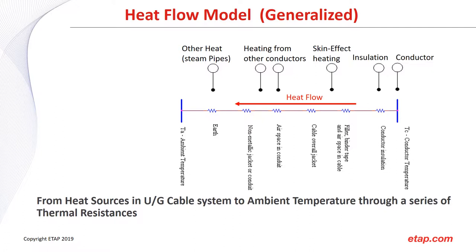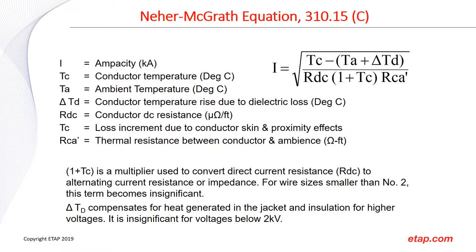The heat flow arrow goes from the conductor temperature, through conductor insulation, through filler, tape, air space in the cable, the cable overall jacket, air space in the conduit, the non-metallic conduit such as PVC, into the earth, and finally into the ambient temperature. All of these barriers need to be taken into account when doing thermal analysis. Both the NEC and IEC standards tell us to use a thermal calculation such as the Neher-McGrath method or the IEC standard.